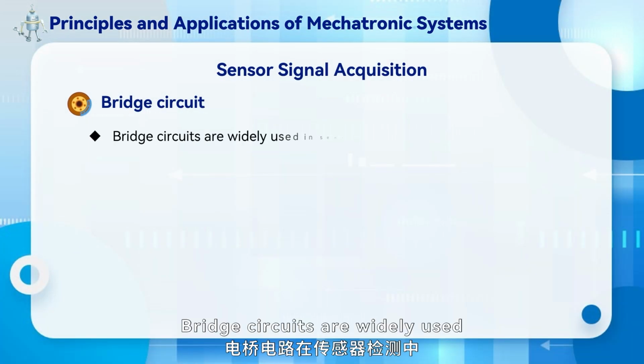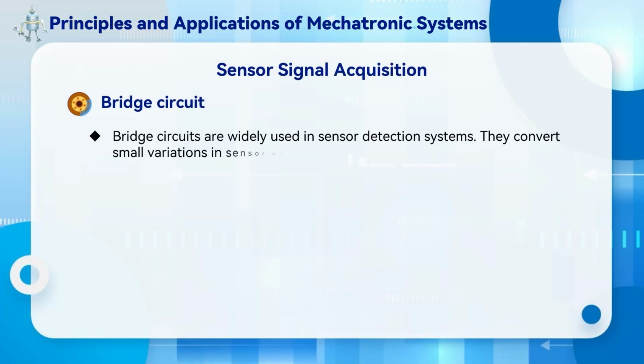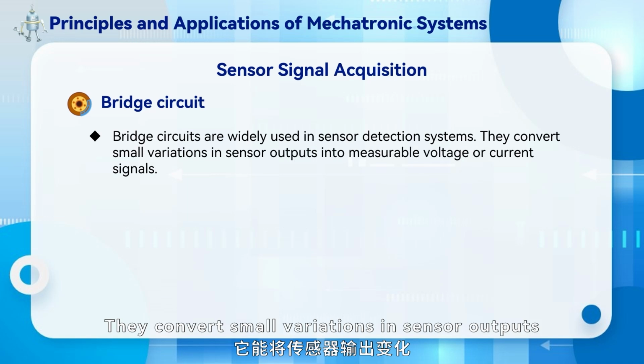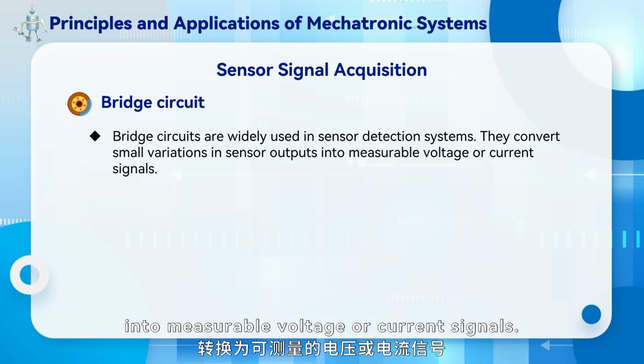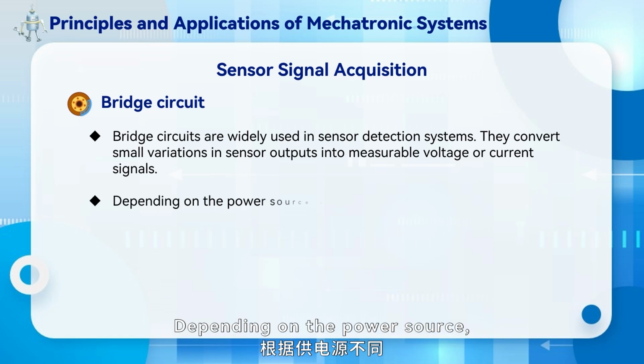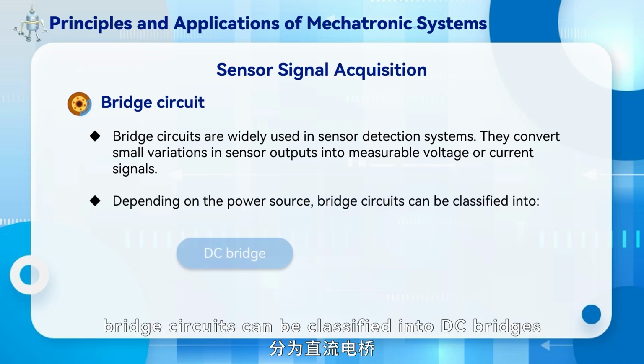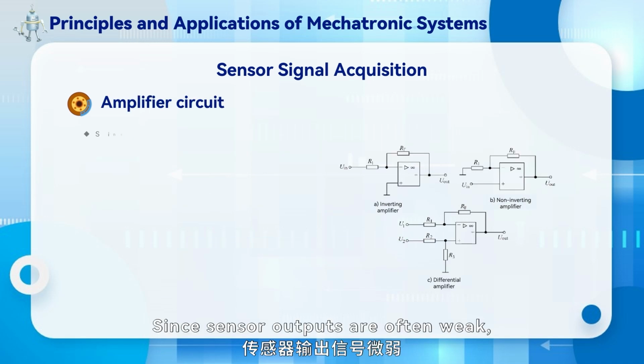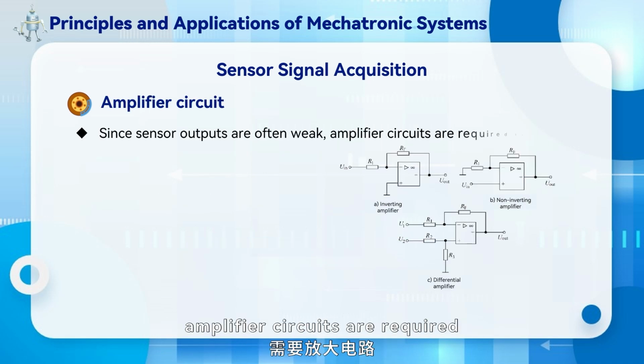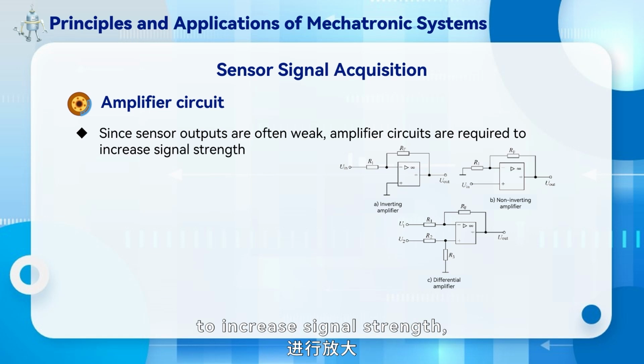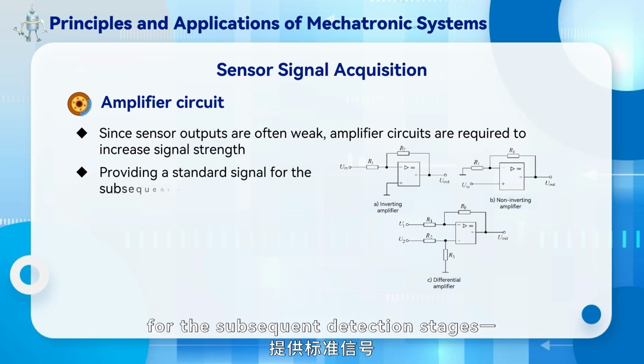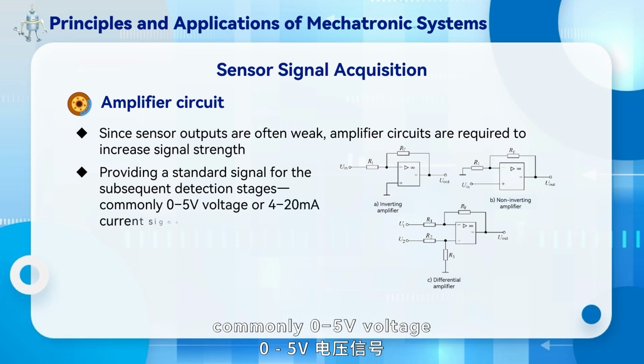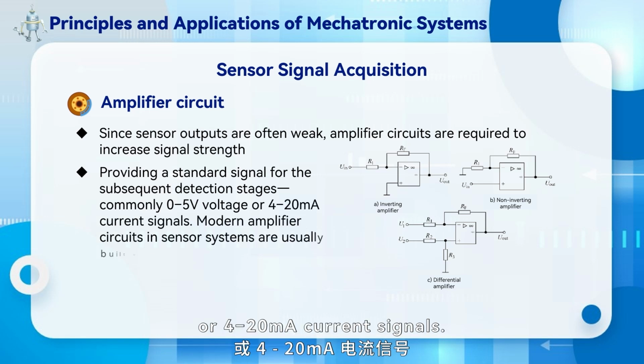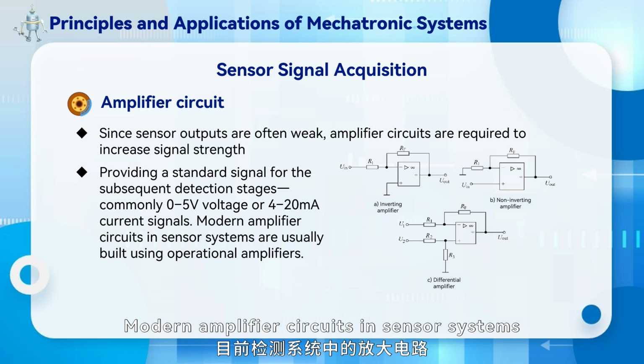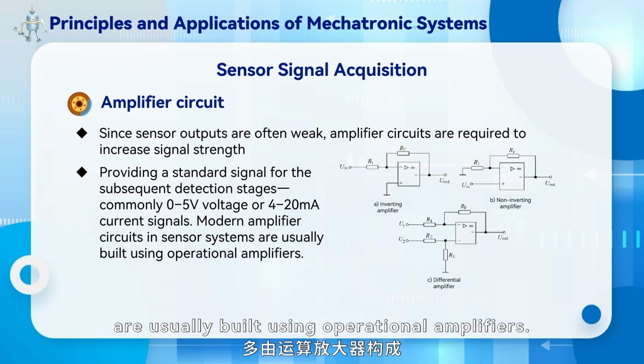Bridge circuits are widely used in sensor detection systems. They convert small variations in sensor outputs into measurable voltage or current signals. Depending on the power source, bridge circuits can be classified into DC bridges and AC bridges. Since sensor outputs are often weak, amplifier circuits are required to increase signal strength, providing a standard signal for the subsequent detection stages, commonly 0 to 5 volts voltage or 4 to 20 milliamperes current signals. Modern amplifier circuits in sensor systems are usually built using operational amplifiers.